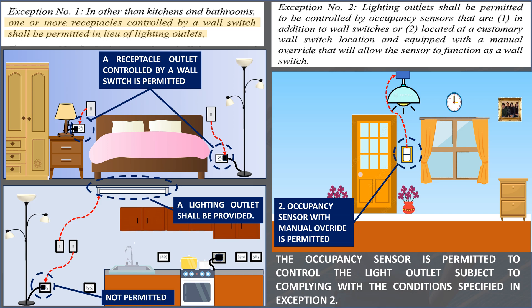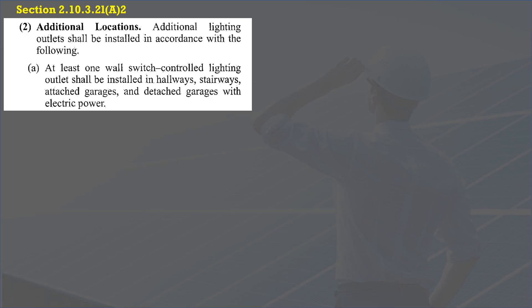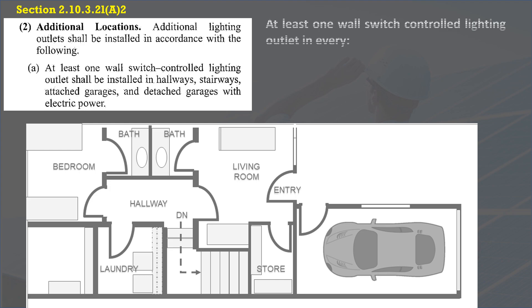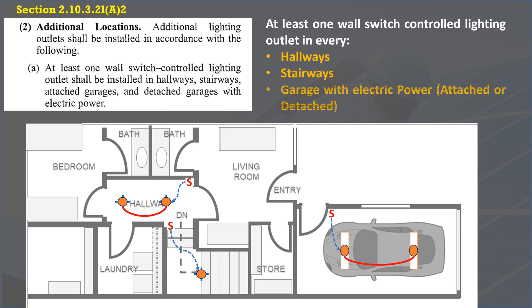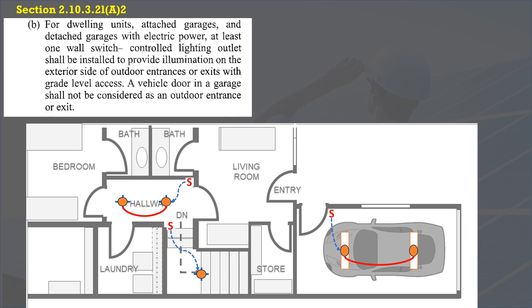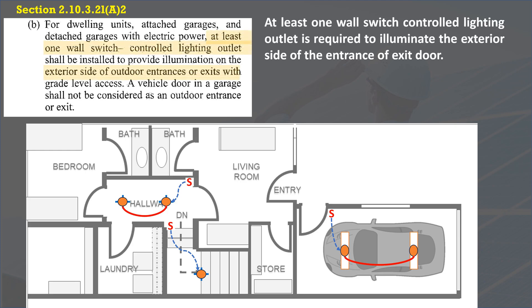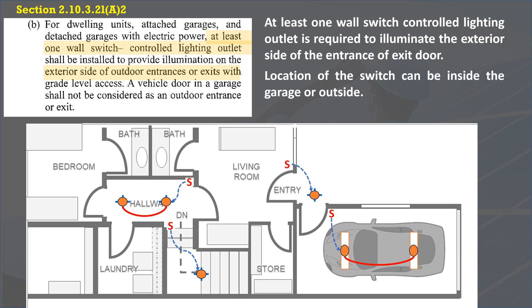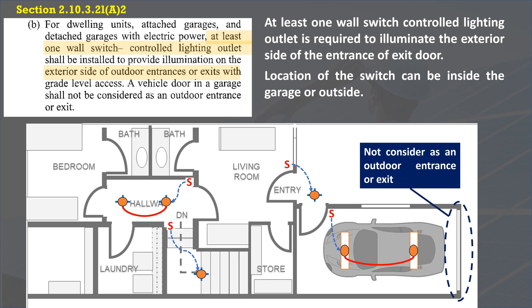Occupancy sensors must be equipped with a manual override. In addition, at least one lighting outlet controlled by a wall-mounted switch is required in hallways, stairways, and garages with electric power, as stated in subsection 2.10.3.21(a)(2)(a). Per subsection 2.10.3.21(a)(2)(b), at least one wall switch-controlled lighting outlet must be installed to provide illumination on the exterior side of outdoor entrances or exits with grade-level access. The vehicle door is not considered an outdoor entrance or exit.